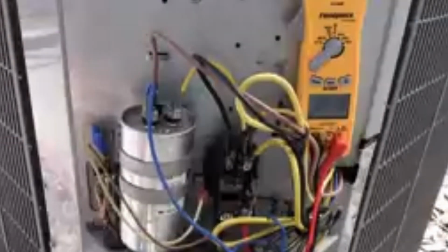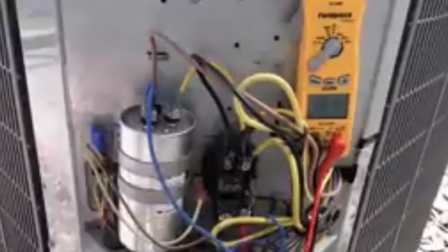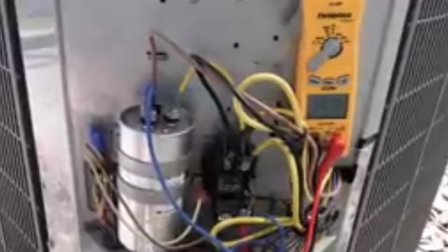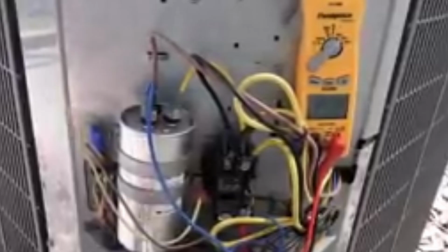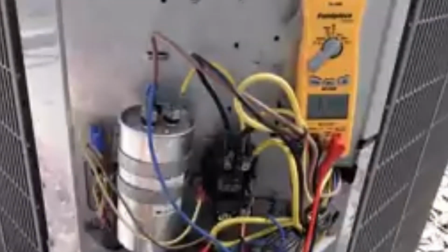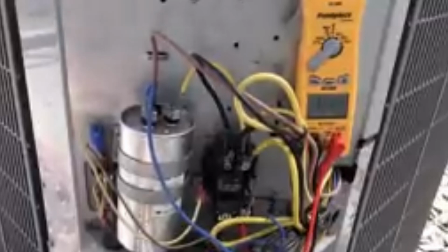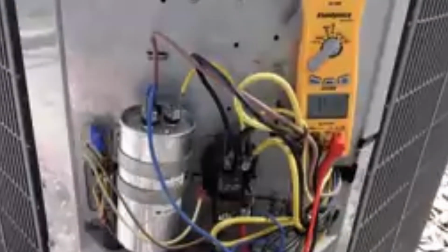And now we're going to use our meter leads to check our incoming voltage as well as our voltage coming out of the top of the contactor, which is how you would confirm that you have potential difference being applied to the loads. Now, obviously we can see that our fan is running and we can hear our compressor running, so we know there is voltage applied, but this is how you would do this measurement.